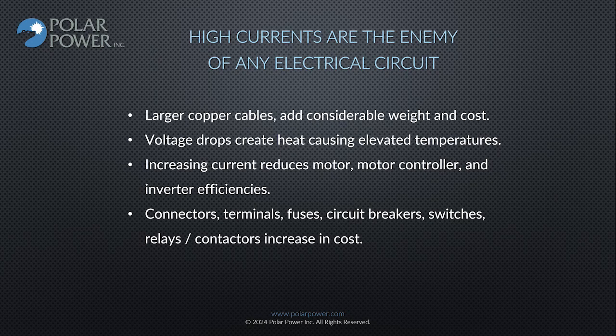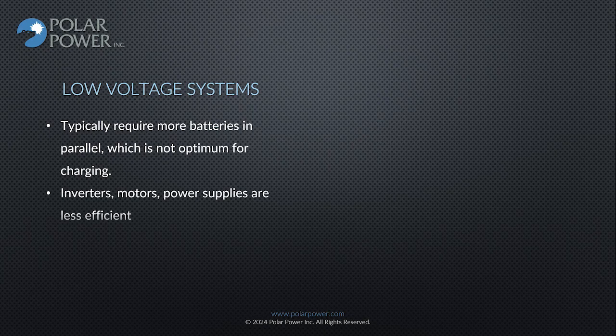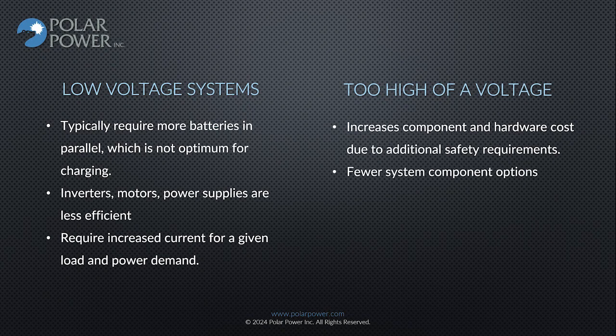High currents are the enemy of any electrical circuit. Larger copper cables add considerable weight and cost. Voltage drops create heat, causing elevated temperatures. Increasing current reduces motor controller and inverter efficiencies. Connectors, terminals, fuses, circuit breakers, switches, relays, and contactors increase in cost. Low voltage systems typically require more batteries in parallel, which is not optimum for charging. Inverters, motors, and power supplies are less efficient. They require increased current for a given load and power demand.